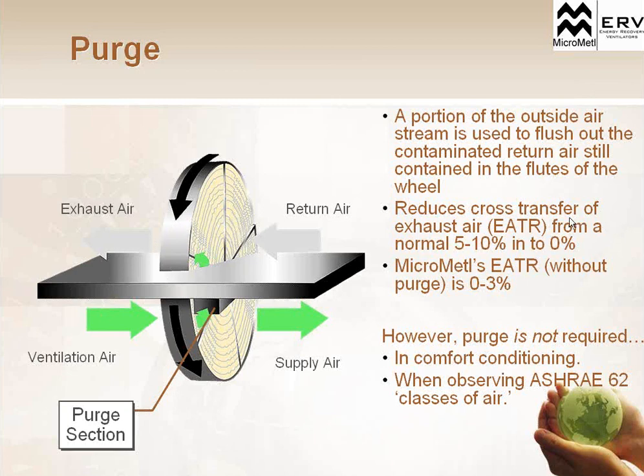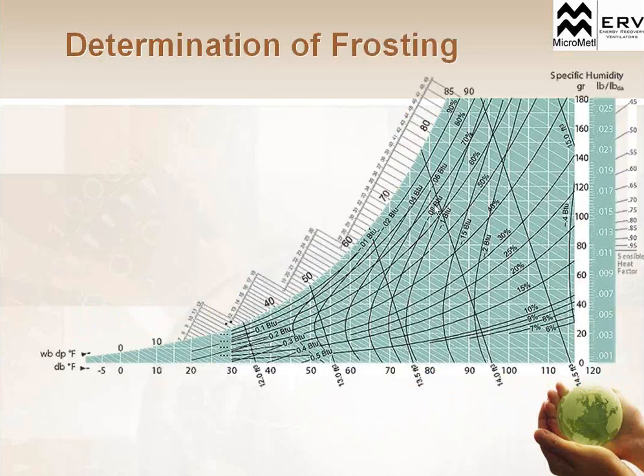That essentially reduces that cross-contamination or that exhaust air transfer. Energy air transfer is the term they use for leakage. So it's EATR, exhaust air transfer ratio. It's the amount of air that sneaks into the system or out of the system before going through the heat exchange wheel.